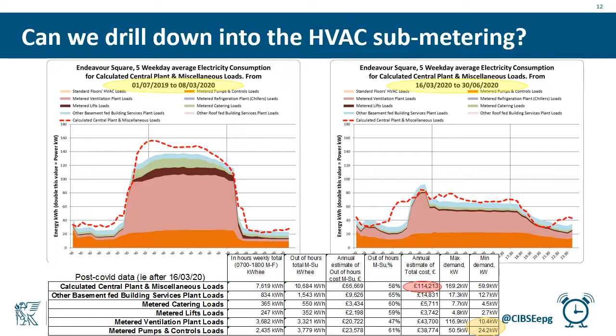We are still investigating with our BMS provider. I had a call with them today, and quite literally they found some meeting room overrides that are kicking in and bringing on HVAC out of hours when they shouldn't be, because essentially it's not been commissioned, since they haven't had this sort of opportunity of an empty building. I think that's probably the biggest takeaway: when buildings get built, you really need that commissioning time so that you can prove that when no one's in the building, the minimum power consumption is happening, and you never get a chance to do that. So it's been a really unique opportunity to capture data.